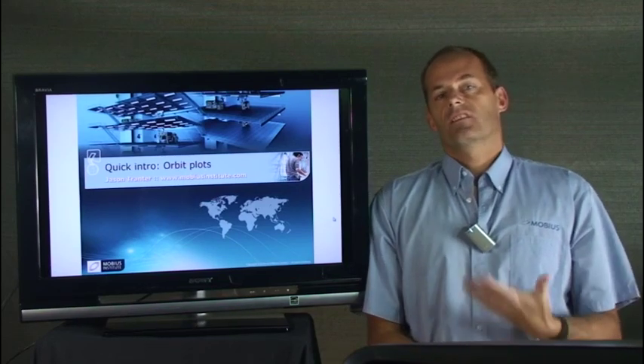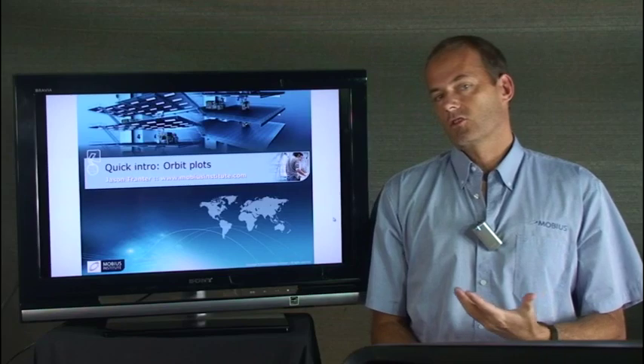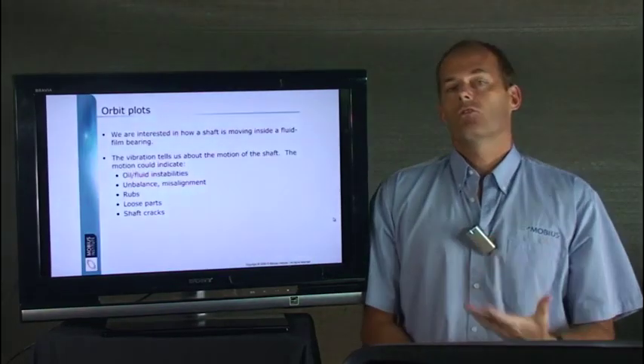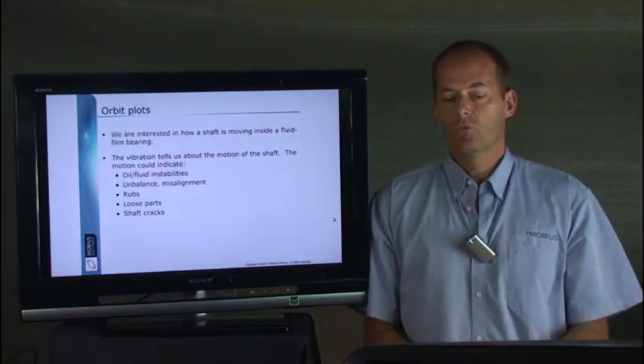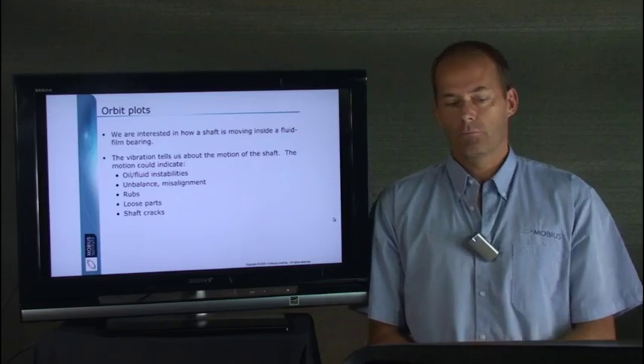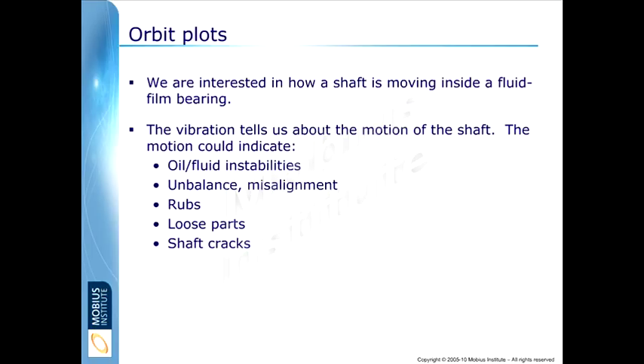Hello and welcome to this quick presentation on Orbit Plots. We are very interested in how a shaft is moving inside a fluid film bearing. The vibration can tell us about the motion of the shaft, and the motion can tell us whether there are oil or fluid instabilities.